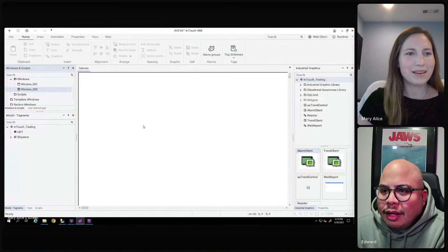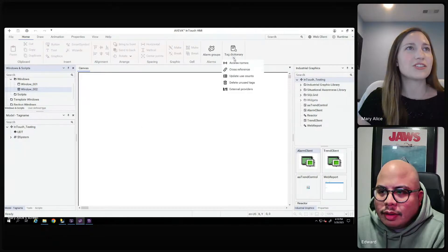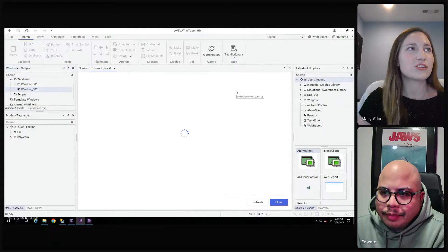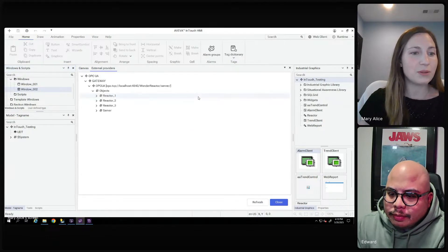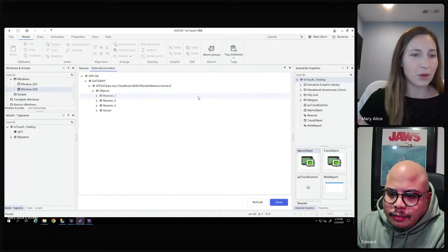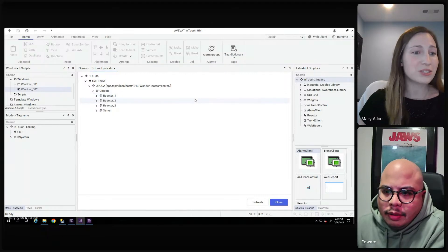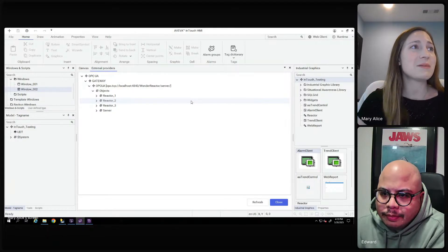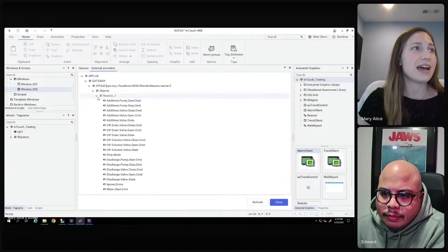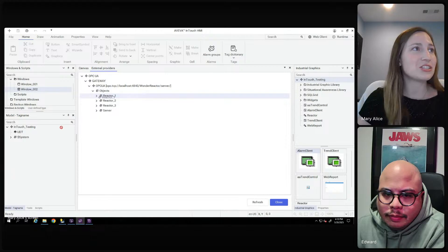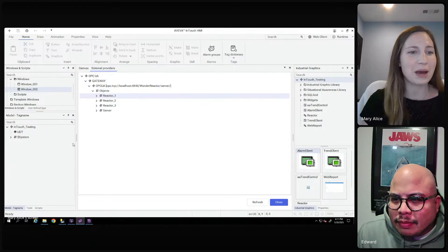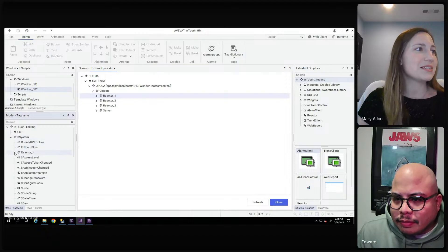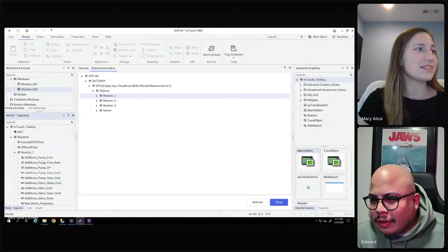Our viewers probably want to see a more in-depth view of this workflow. Let me share my screen. In the InTouch application, I can expand the arrow under Tag Dictionary, click External Providers, and it connects to my OPC UA server. I can see all my tags and areas within my OPC UA server — all the data collected from my plant. It's as simple as dragging Reactor One and all of its tags into the Model Tag Name pane. I have about 70 tags and in just seconds they're all part of my InTouch application.